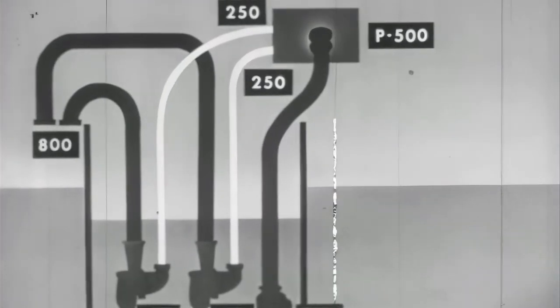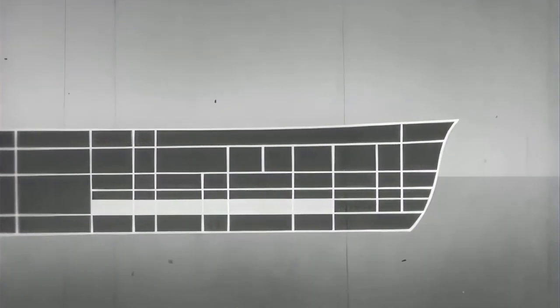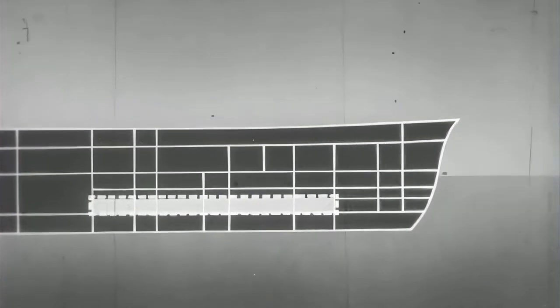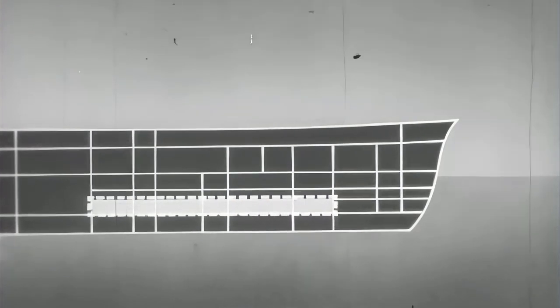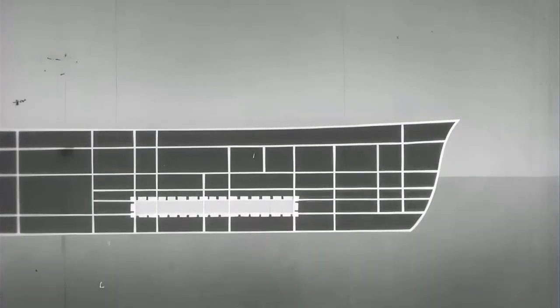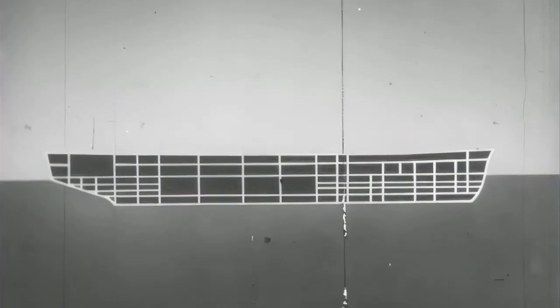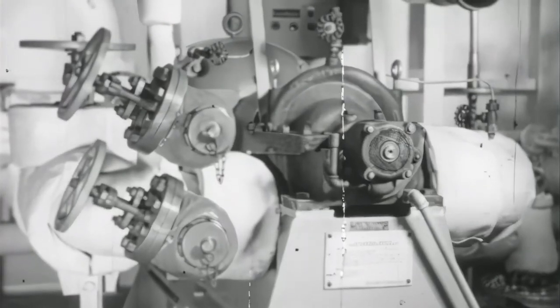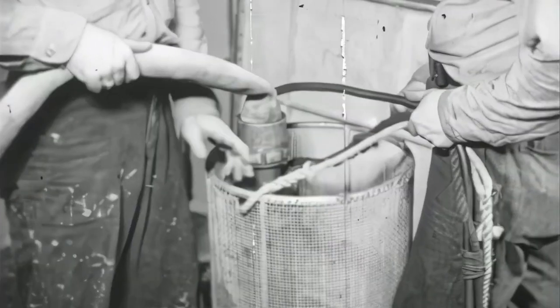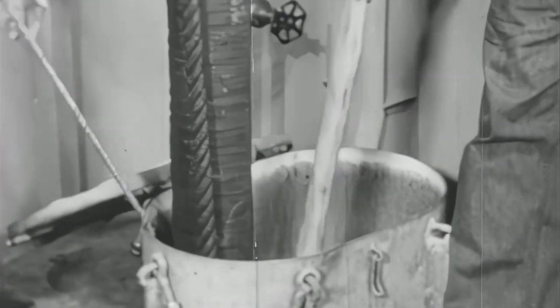With combinations like these, you can handle almost any unwatering problem. When faced with flooding, attack the problem logically. First, set up flooding boundaries. Second, restore watertightness by plugging all leaks. Third, pump out, giving priority to loose water and higher compartments. Fourth, work from the fringes toward the center of damage. The answer to progressive flooding is progressive unwatering. Learn all there is to know about the installed and portable equipment and the methods of unwatering flooded compartments, and put that knowledge into practice. It's too late to learn after flooding starts.